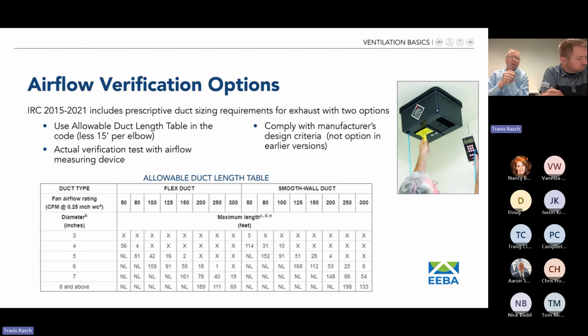As evidence of why this is important, all of the residential codes, IRC since 2015, have this duct sizing chart. If you can see this table at the bottom, in the upper left-hand corner, it says to use the fan airflow rating at 1/4 inch of static pressure. Again, you should go to the product spec sheet or the HVI certified products directory and find that level. In the example of a bath fan where you need to move 50 CFM per code, in that first column, flex duct, 50 CFM, 3-inch diameter, there's an X there. That means it's not allowed. You're never going to move 50 CFM with a 3-inch ducted product, is what the code is saying. You have to move to at least 4-inch ducting, and there you're allowed 56 feet.